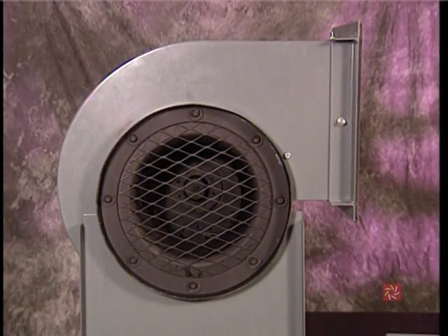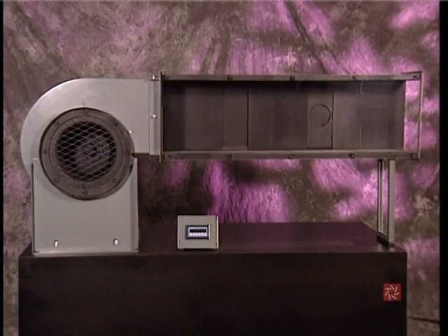Normally, a fan is tested with an open inlet and a section of straight duct attached to the outlet. This setup results in uniform airflow into the fan and efficient static pressure recovery on the fan outlet. To observe the movement of air molecules in the duct, we've introduced helium-filled bubbles into the airstream.